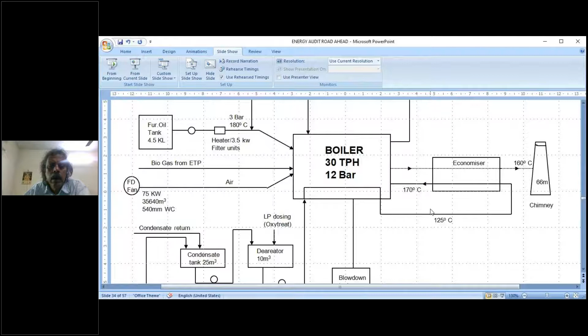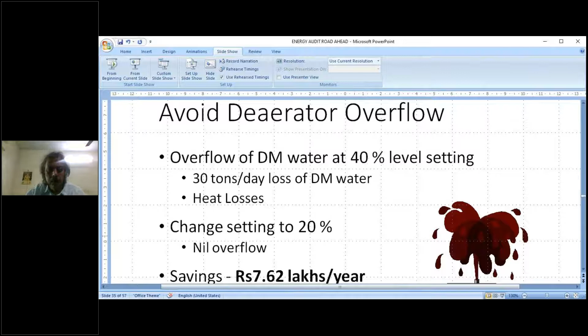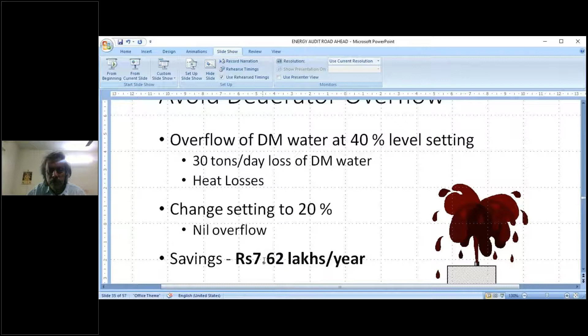So on analysis, as you walk through, we find a place where some water was flowing, and when you probe that, we find that the deaerator water is overflowing. Overflow water is going into a drain because of some changes in the level setting. That level setting was 40%, which led to overflows. And nobody knows because it is going into an underground closed drain. The pipe is put into an underground drain so that it should not flash, but then nobody can observe that. So on an audit, you find that this is a simple wastage which is happening. By changing the overflow setting from 40 to 20, the saving is about 7 lakhs.